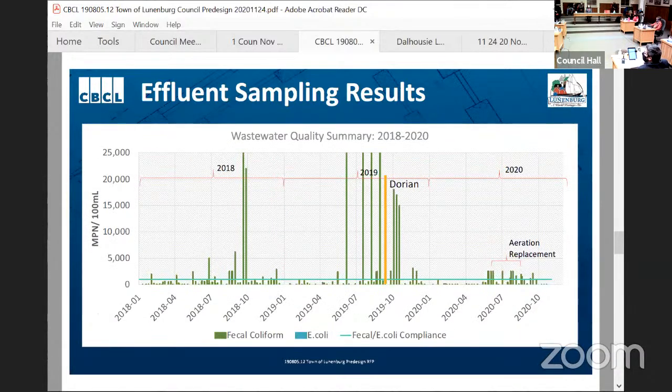There was also an improvement with regard to the bacterial sampling. So this one is fecal coliforms and E. coli. You can see that in 2018, 2019, at times, especially during the summer when it's the most difficult treatment conditions, the plant was considerably exceeding the bacterial requirements.